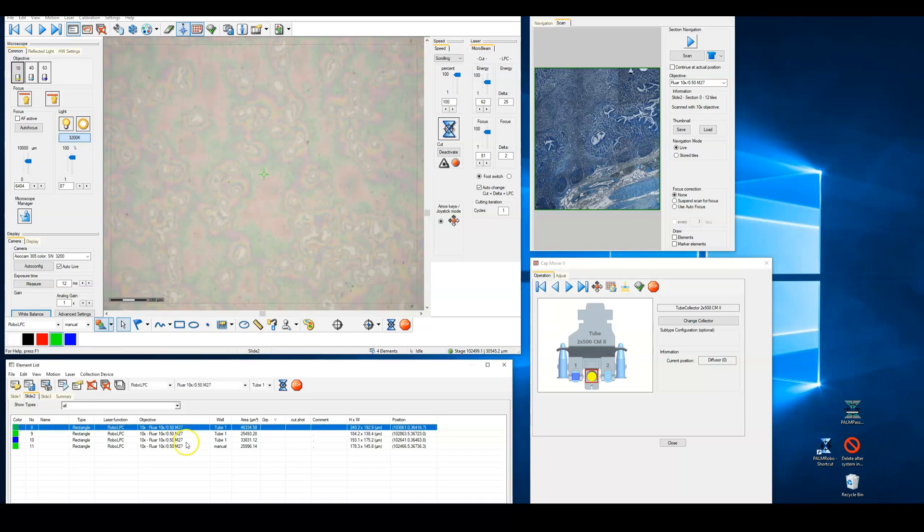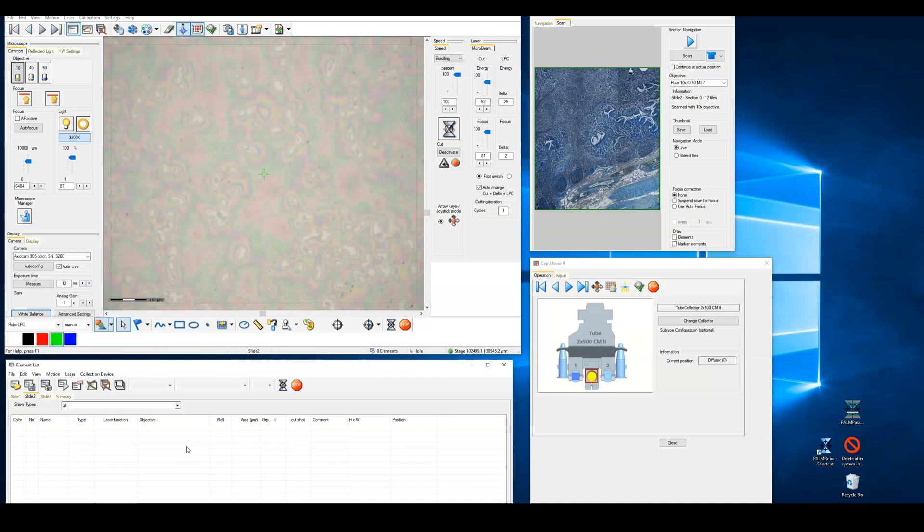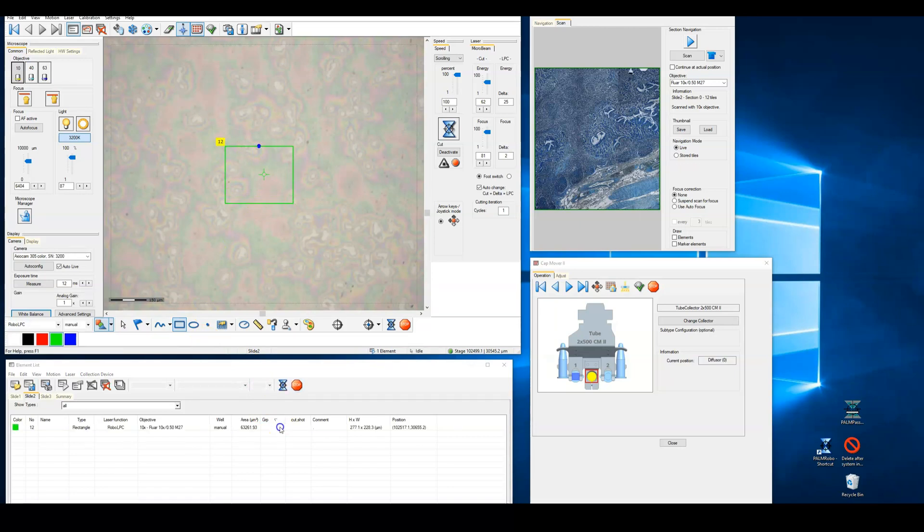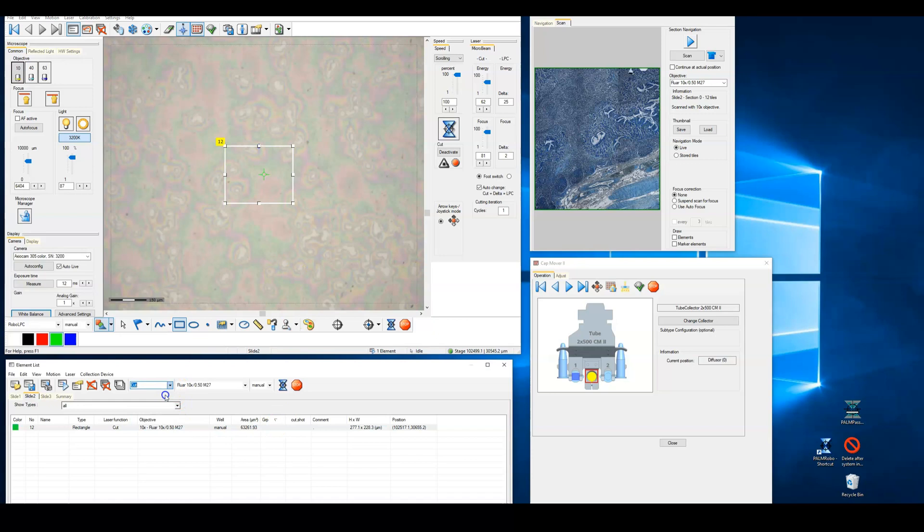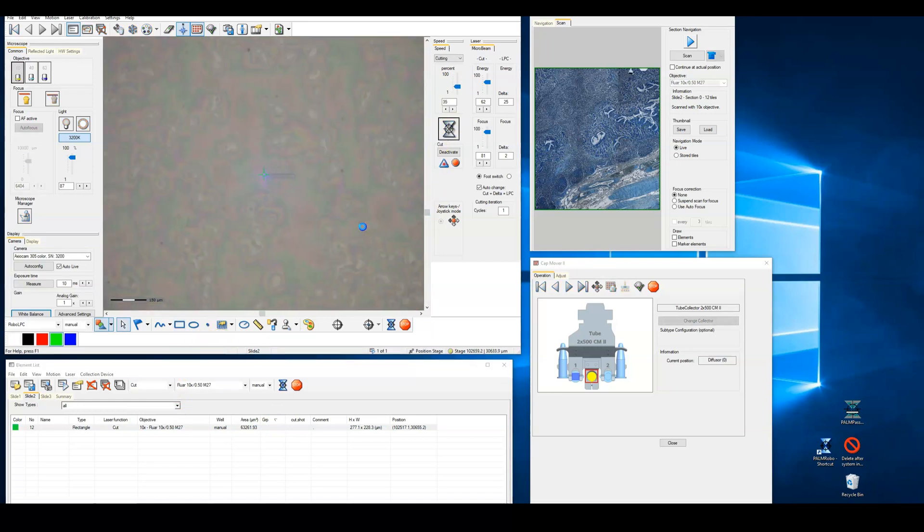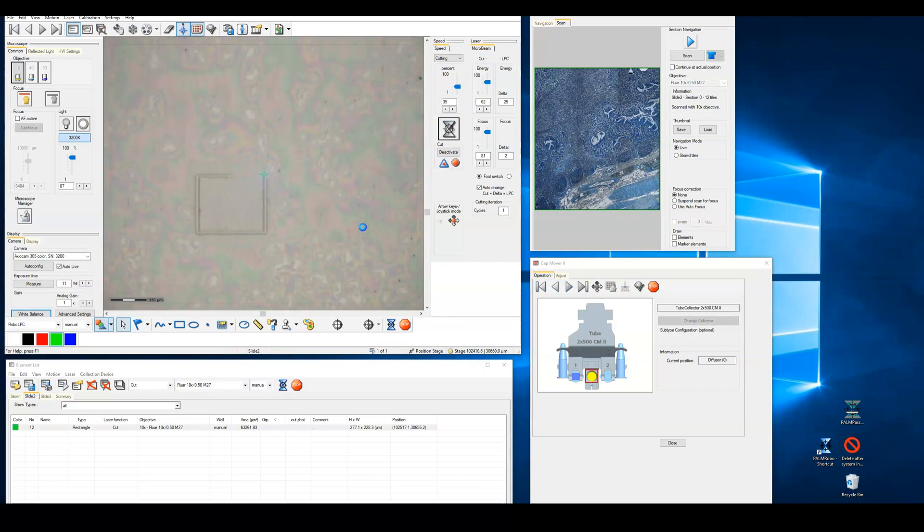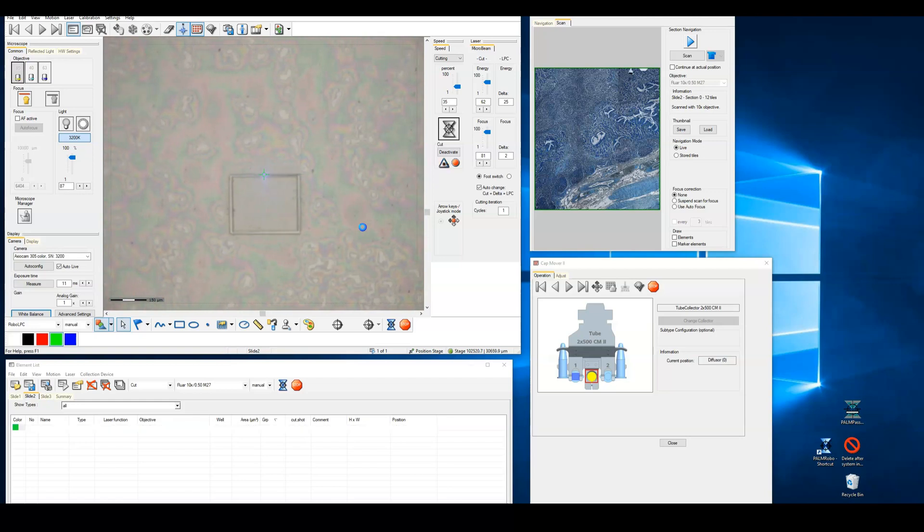In any laser capture micro dissection session, I would strongly suggest that the first cuts you make are on a region of the membrane slide with a simple square. If the cut made is of good thickness and the cut path travels along the drawn square exactly, you can immediately proceed to your tissue and optimize your cut there. If you're not satisfied with the cut, or there is no cut, then you'll need to adjust the laser power and potentially the laser focus.